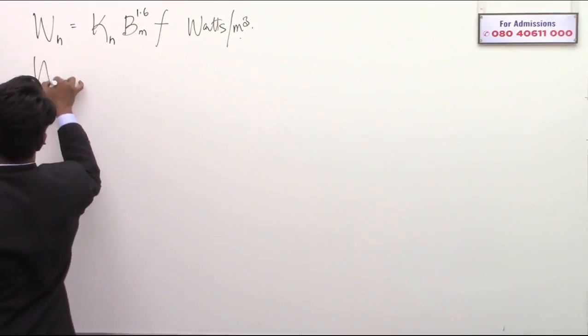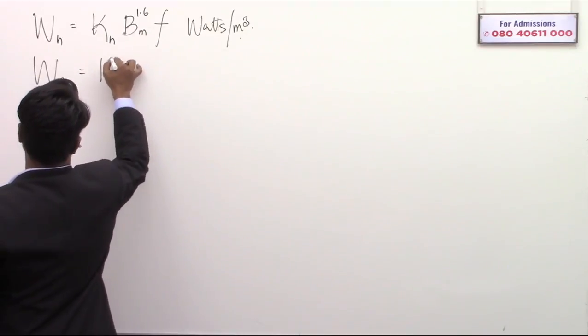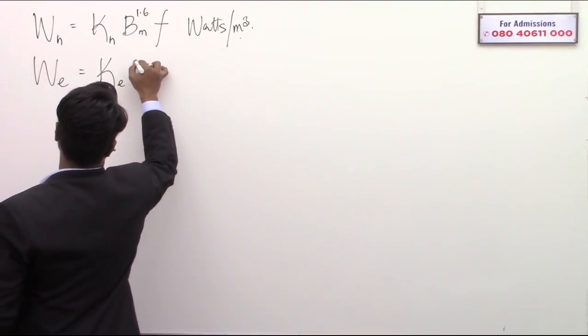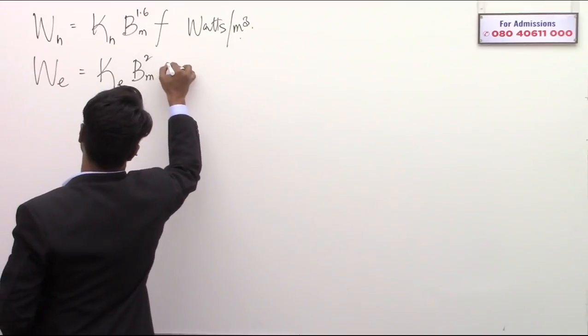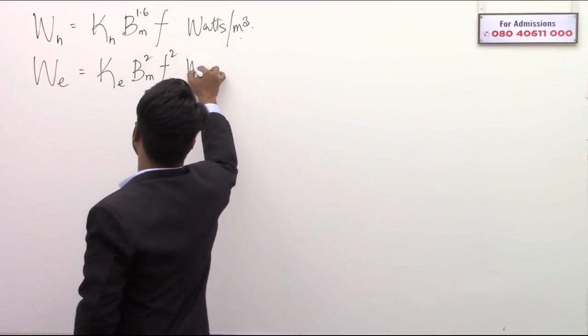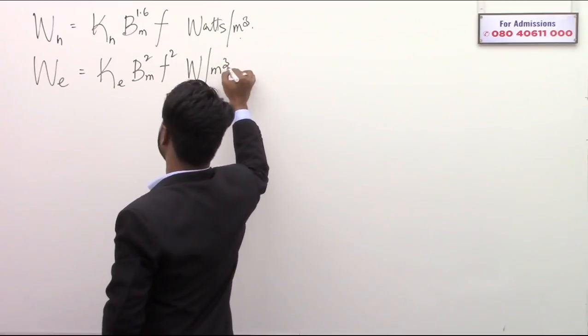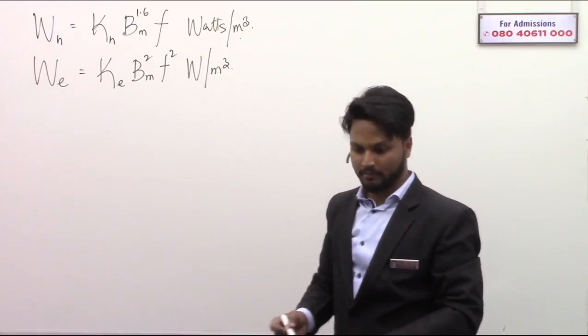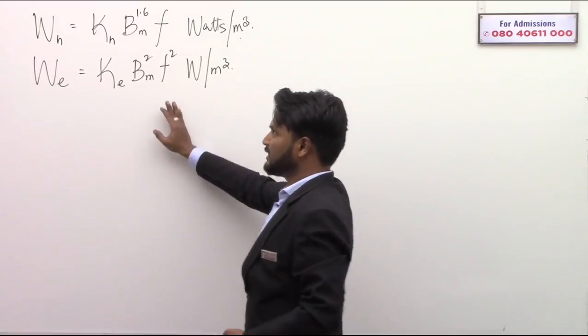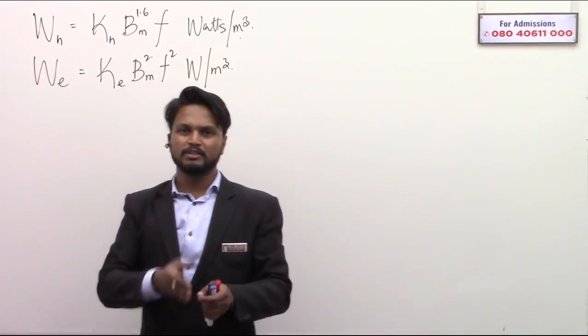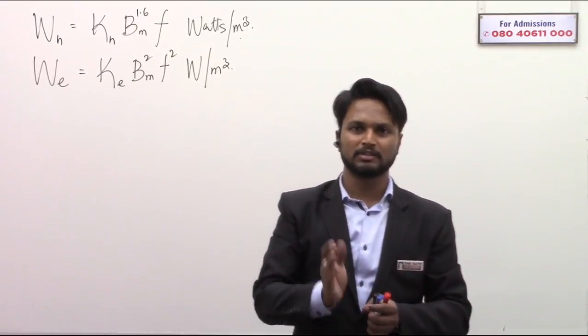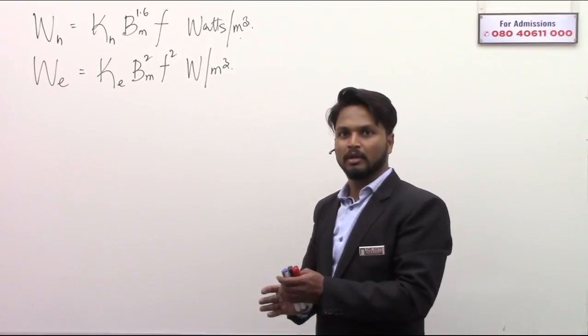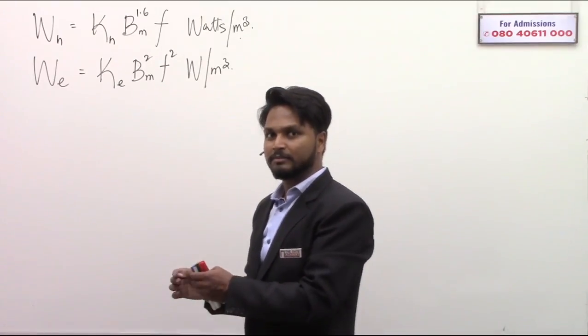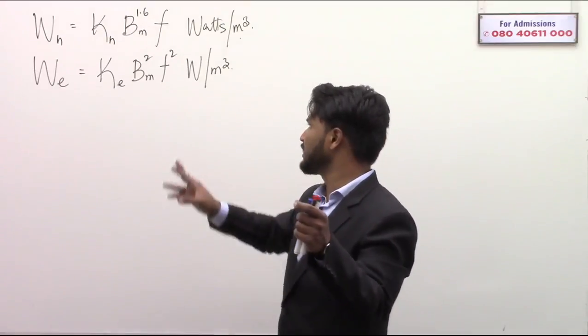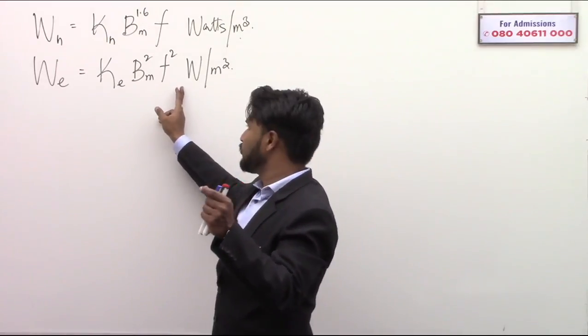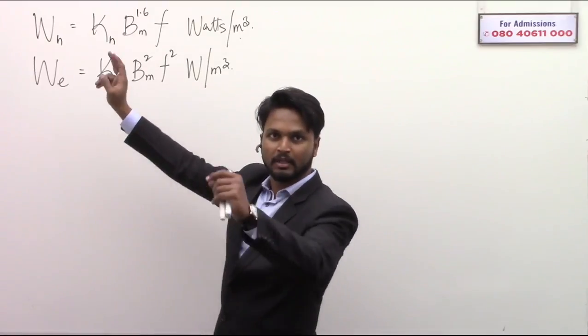And eddy current losses is equal to Ke multiplied by B max whole square into F square watts per meter cube. You might be thinking about T square, thickness square. Here, once you have sliced the core into laminations, the thickness of the laminations is a constant. I'm just including that thickness square, T square, in Ke only.